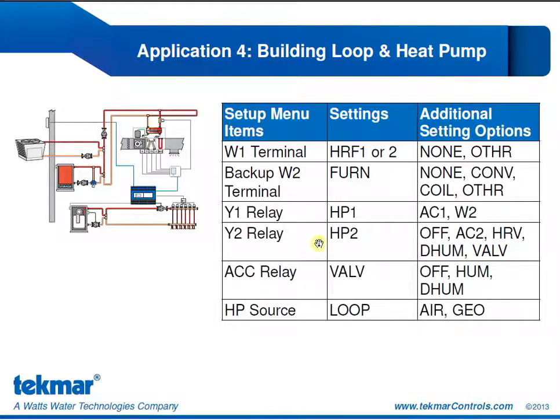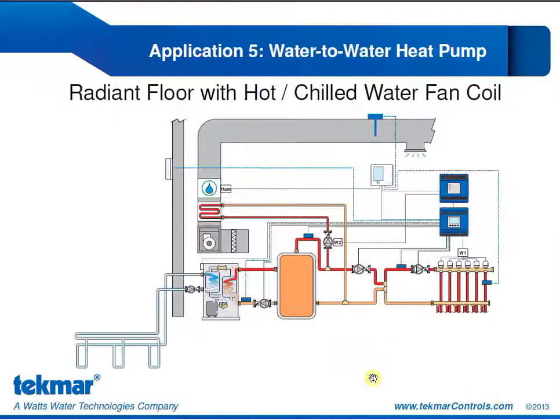Here are the essential settings for this application. If we include the radiant, W1 terminal, HRF 1 or 2. The backup W2 terminal is set to furnace for the electric strip. Y1 and Y2 relays are configured for our heat pump stages 1 and 2. This time our accessory relay is controlling the valve, and the heat pump, it's a loop.